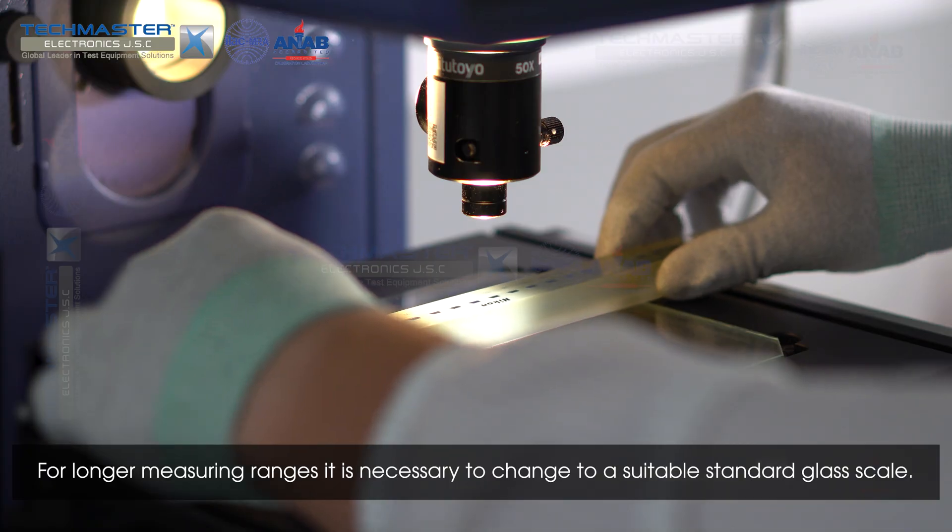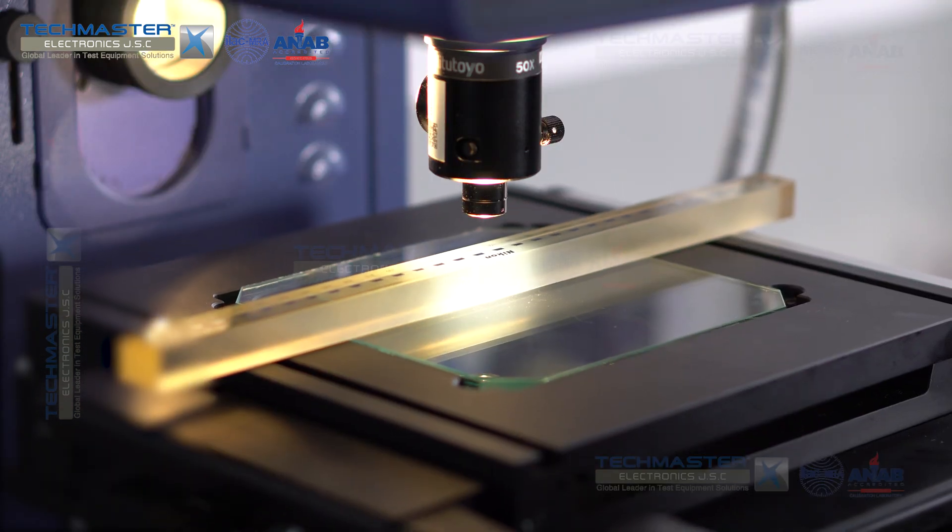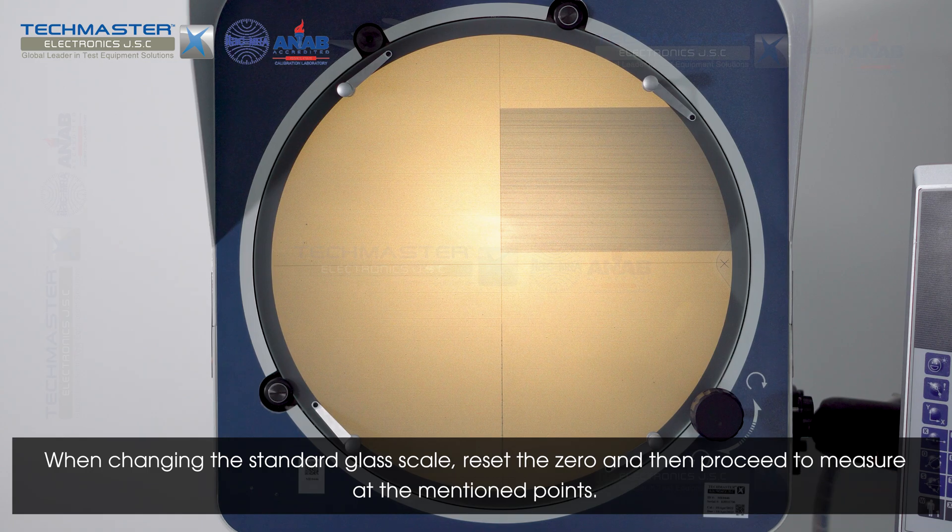For longer measuring ranges, it is necessary to change to a suitable standard glass scale. When changing the standard glass scale, reset the zero and then proceed to measure at the mentioned points.